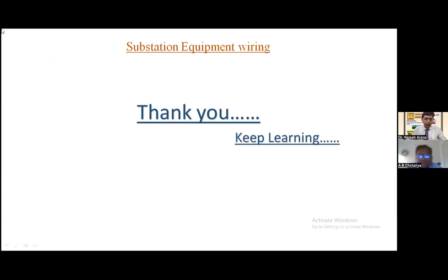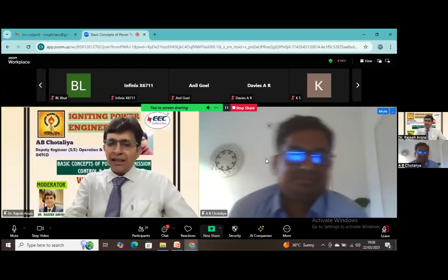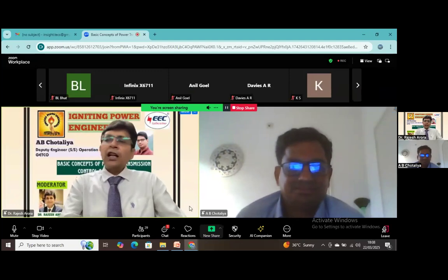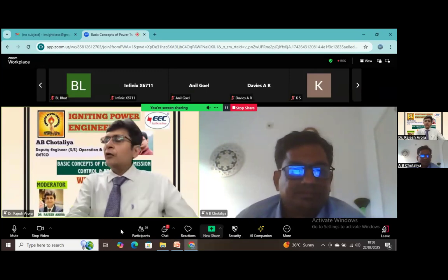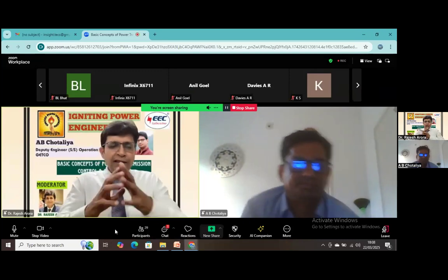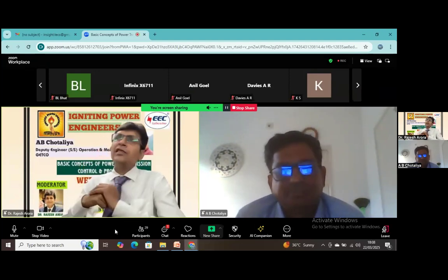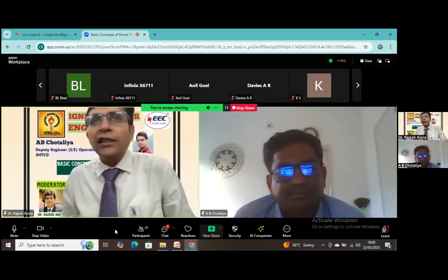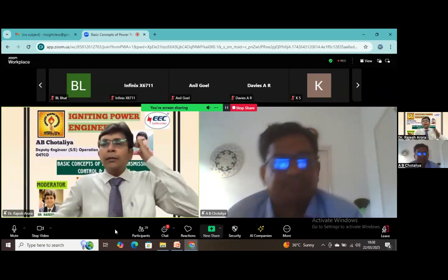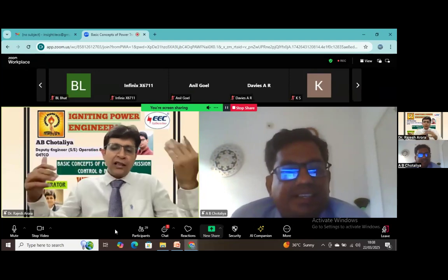Thank you, Abhishek ji. I would like to say that that was very informative, direct from the field. You have given the practical aspects, insightful, and last but not the least, an excellent presentation from your side. You tried to cover almost all the things required as far as control and protection systems of the transmission system are concerned. I would like to add three things. You have mentioned that CTs have three cores. In a big substation, it has four or five cores, depending on the applications and the network you have.